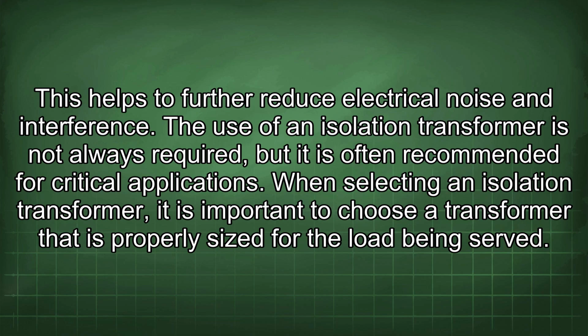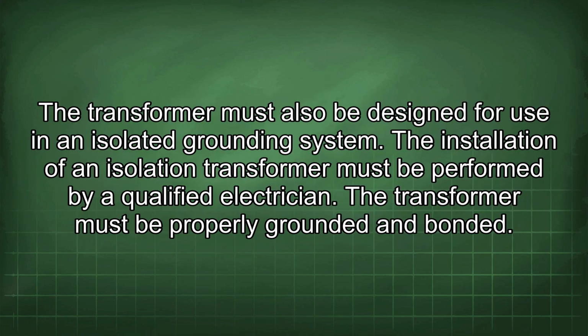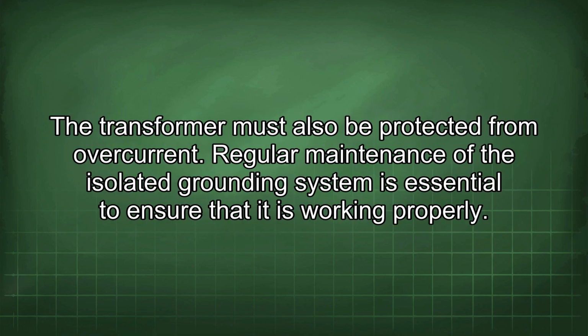When selecting an isolation transformer, it is important to choose a transformer that is properly sized for the load being served. The transformer must also be designed for use in an isolated grounding system. The installation of an isolation transformer must be performed by a qualified electrician. The transformer must be properly grounded and bonded. The transformer must also be protected from overcurrent. Regular maintenance of the isolated grounding system is essential to ensure that it is working properly.